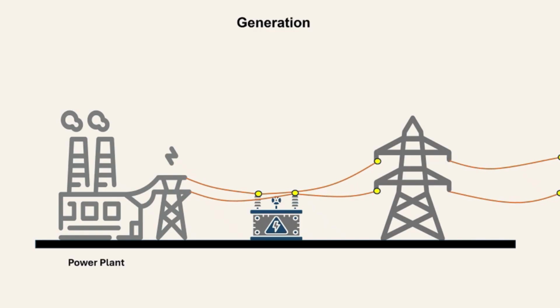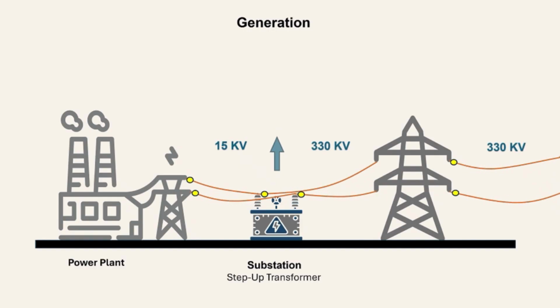Power is generated from the plant at 15 kilovolts, but this voltage is not nearly enough for long distance transmission. So, the power goes to a step-up substation. Here, transformers boost up voltage from 15 kilovolts to 330 kilovolts. Why? Because the higher the voltage, the less energy gets lost along the way.